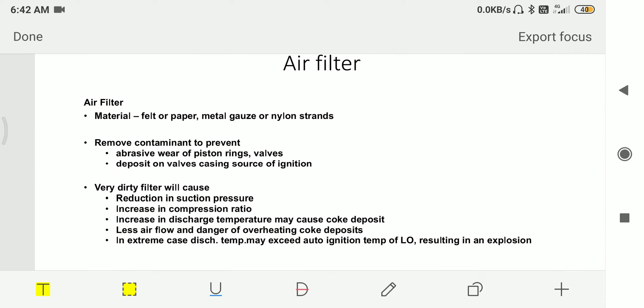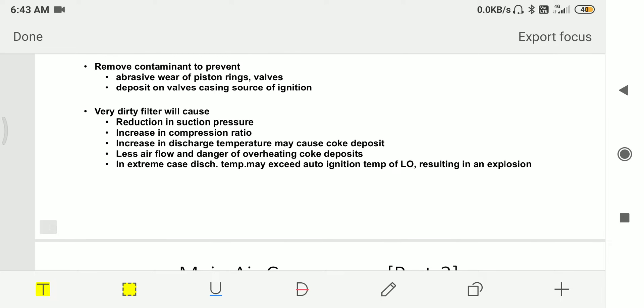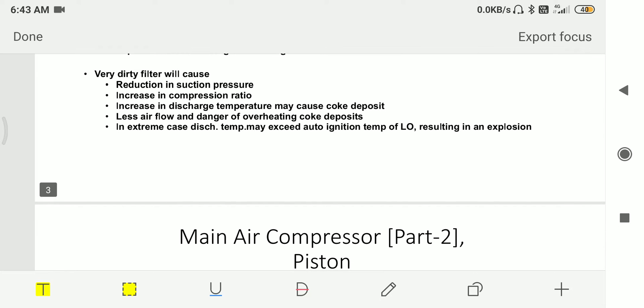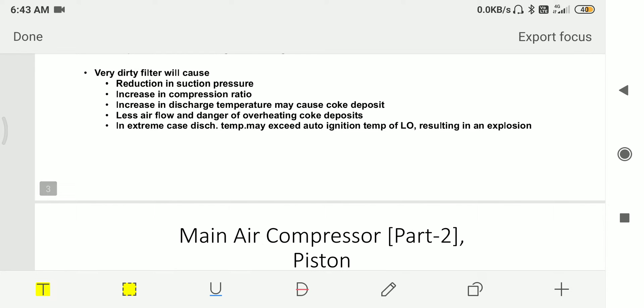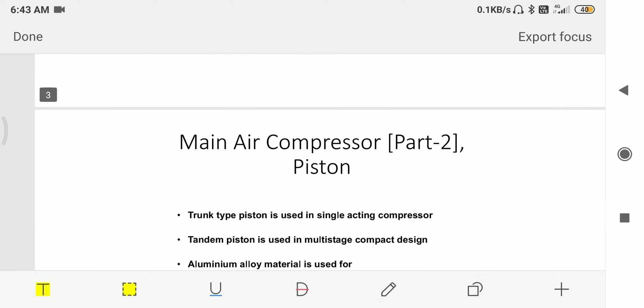The first component is air filter. The material used for the air filter is felt, paper, metal gauze, and nylon strands. These air filters remove contaminants to prevent abrasive wear of the piston rings and valves, and deposits on the valves casing which could be a source of ignition. If the filter is very dirty, it will cause reduction in suction pressure, increase in compression ratio, increase in discharge temperature, less air flow, and danger of overheating and coke deposit. In extreme cases, discharge temperature may exceed auto ignition temperature of the lube oil, resulting in an explosion.